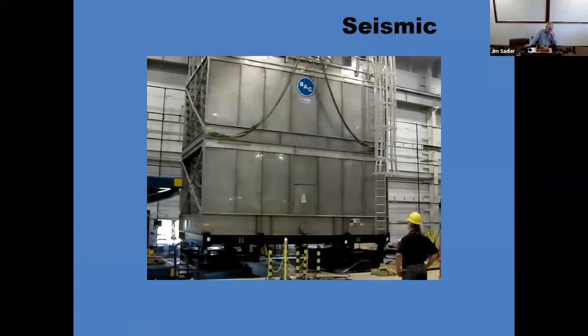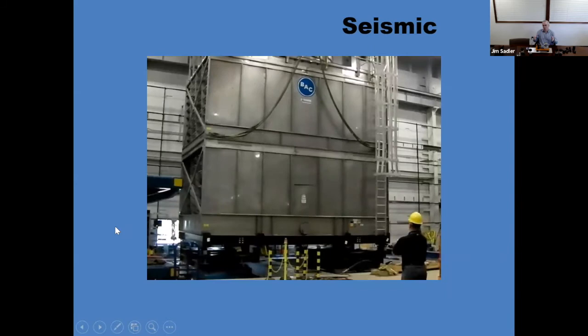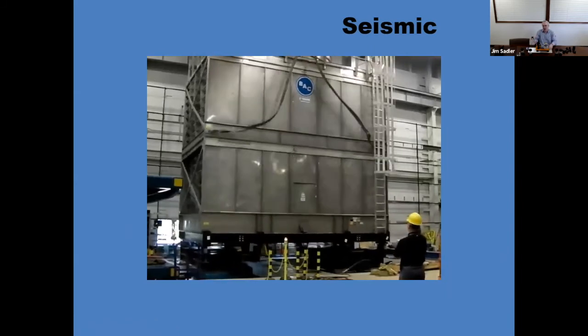So you may have the same requirement where you are if you're in a high seismic zone, but in the United States, in California, they insist that the equipment survive a simulated earthquake. So they take the equipment, they put it on a shaker table test, they bring it back to their factory, make sure it's operational, and if it is, it passes the test. So this is just a video of one of those tests we were involved in. This is a cooling tower on a shaker, simulating an earthquake.